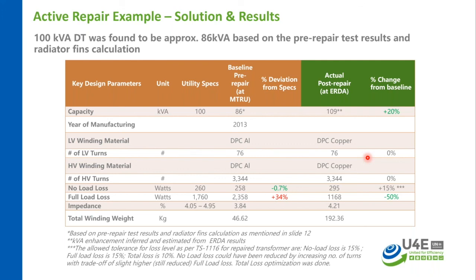So 100 kVA transformer, where the medium voltage is 11 kV, the secondary voltage is 433 volt. It's a delta star transformer. The kVA capacity of this transformer when it was assessed through the software was 86 kVA. And we realized that the reduction of the kVA capacity is mainly due to the insufficient cooling, and also while doing the previous repairs on the transformer, this transformer was repaired 2 times earlier. We have seen that some of the less material was put back in the transformer. As a result of that, the kVA capacity was lost.